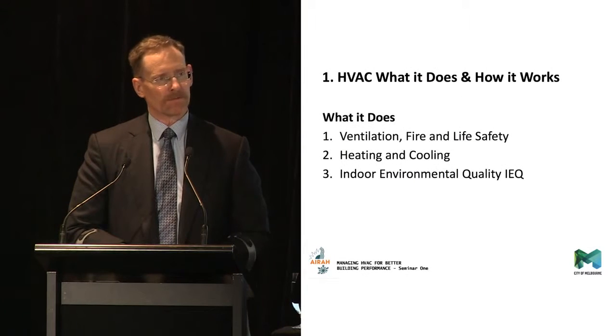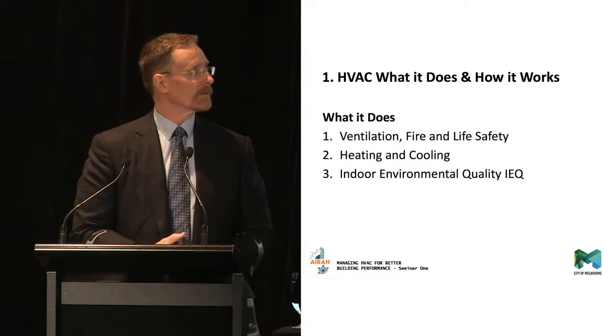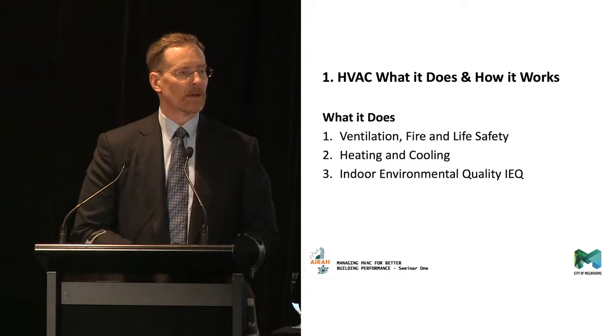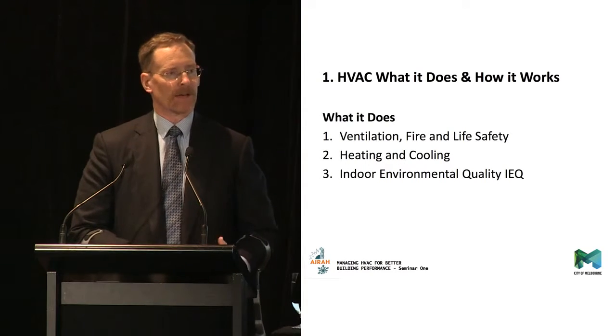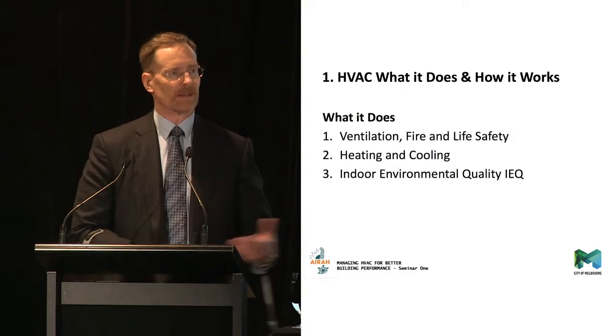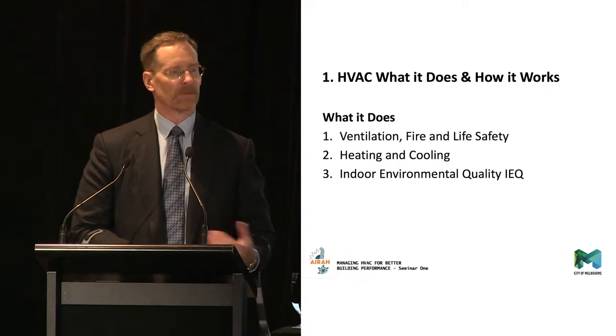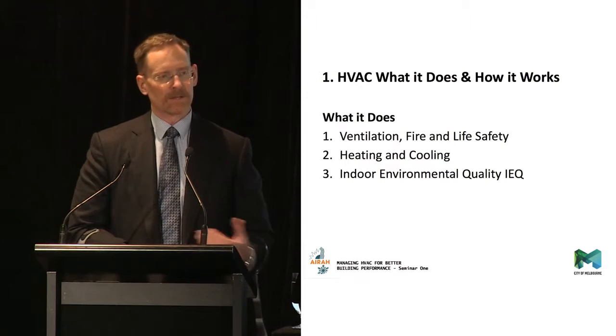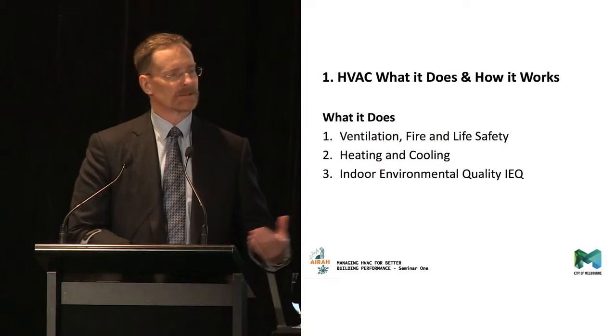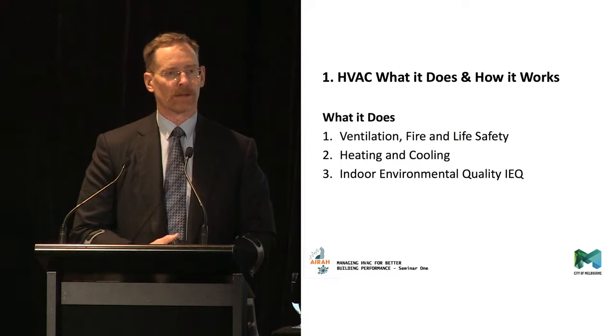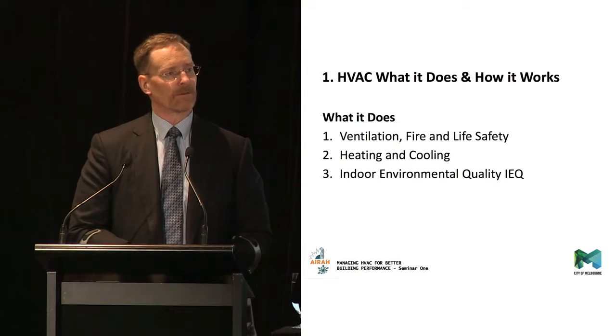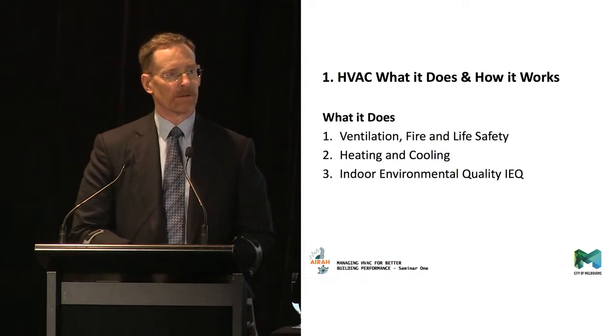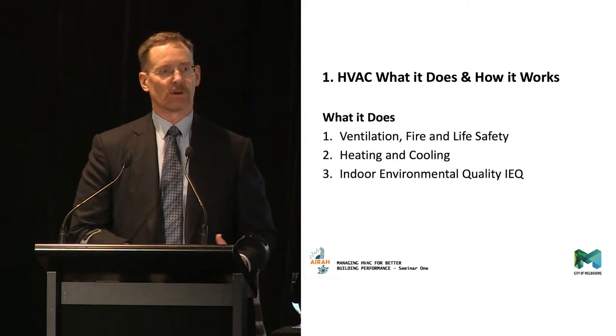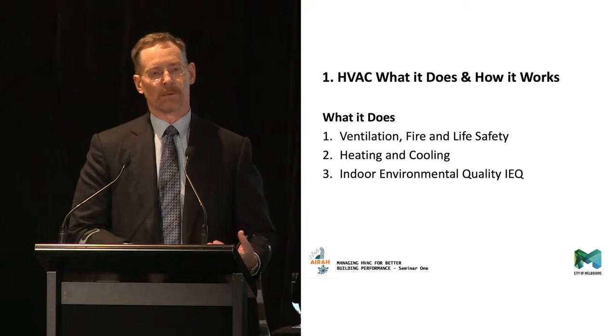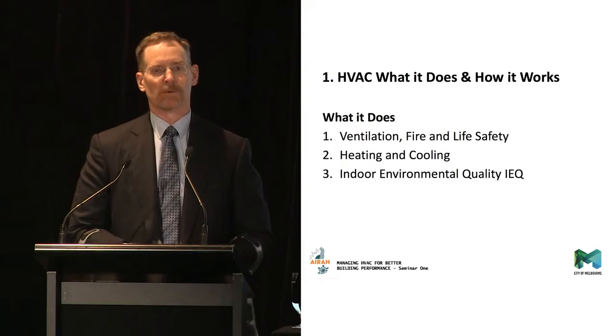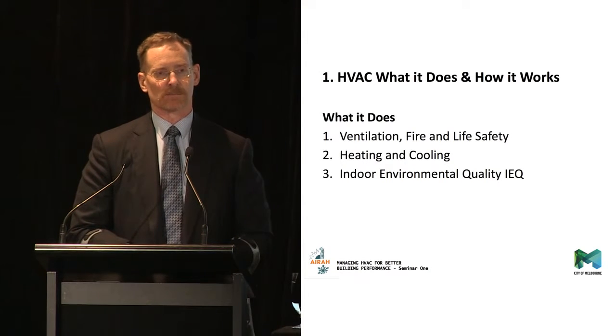In the first instance, it provides ventilation. In the space we're in today, there's no openable windows. For health, for safety, for comfort, we rely upon the air conditioning system ventilating the space, providing outside air, providing clean air. As an interesting aside, these systems also have an important role in fire mode. When the building goes into fire mode and smoke's being generated, the ventilation systems need to be designed to remove the smoke and make a safe path of egress so people get out safely.